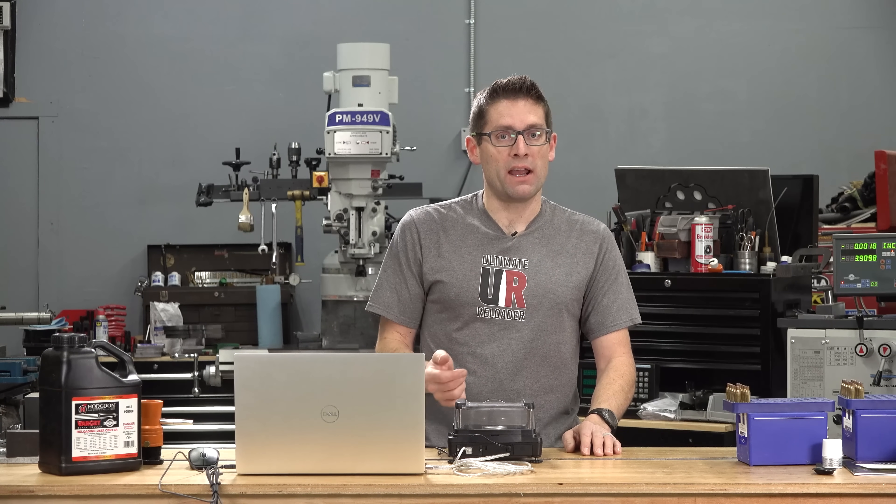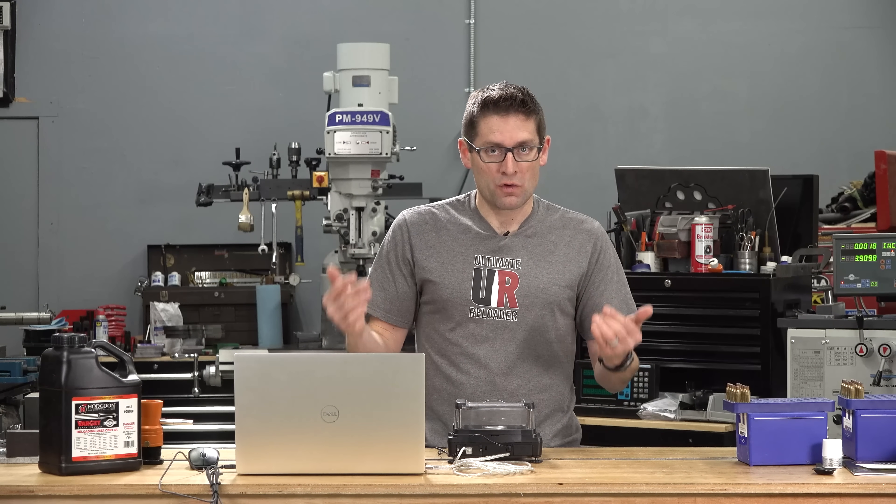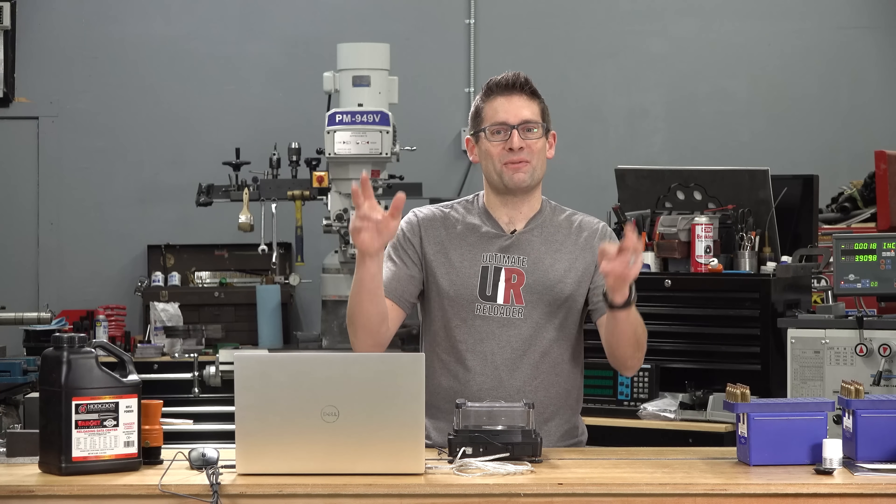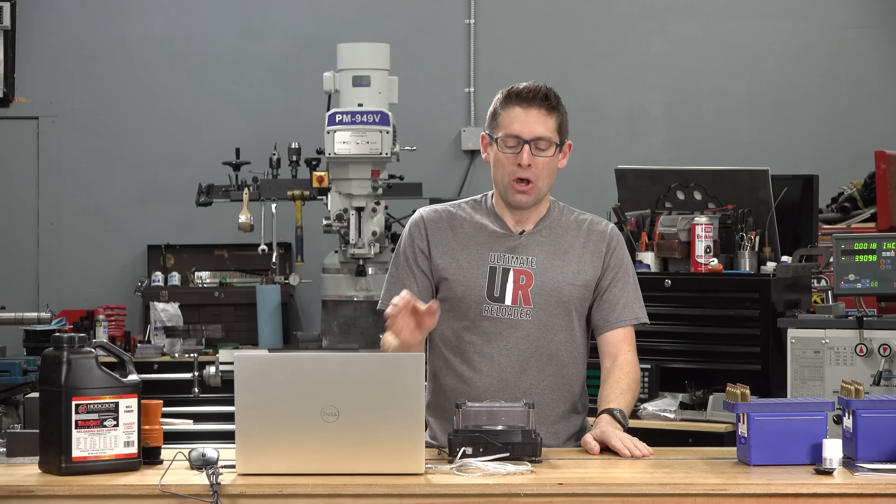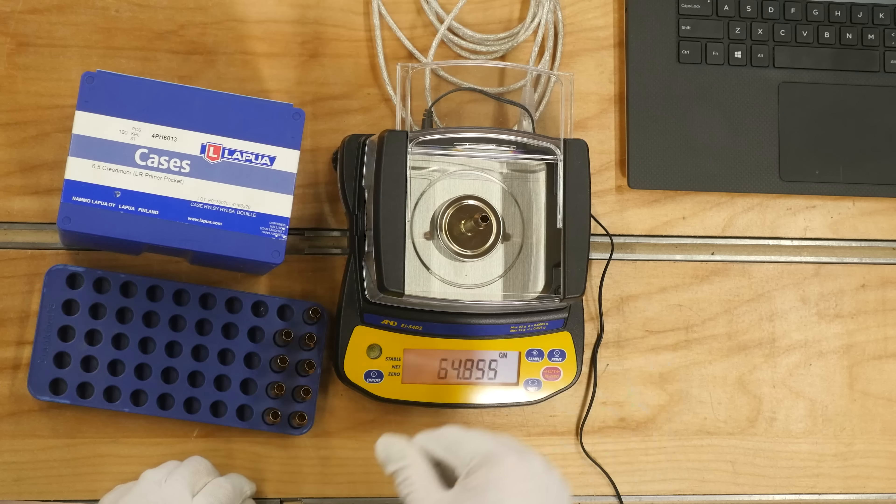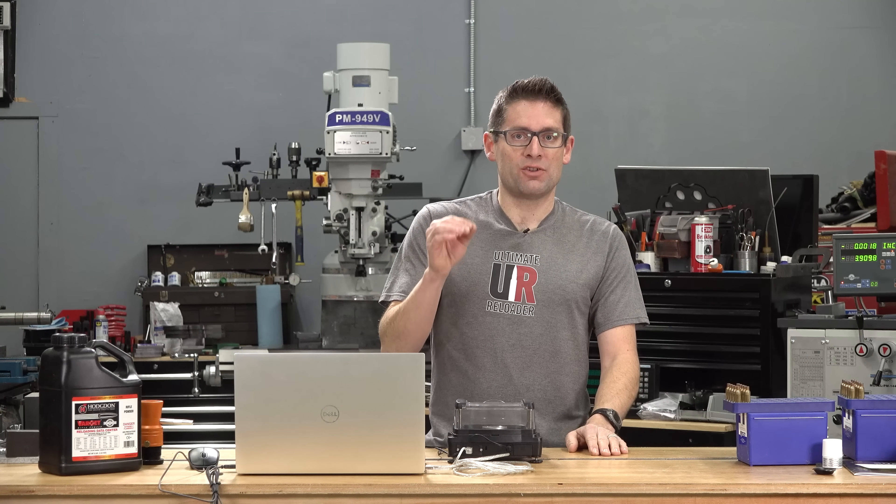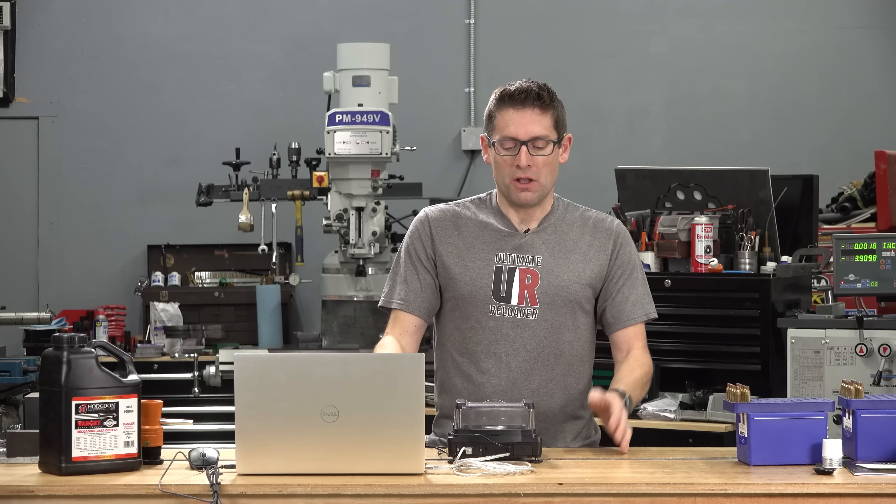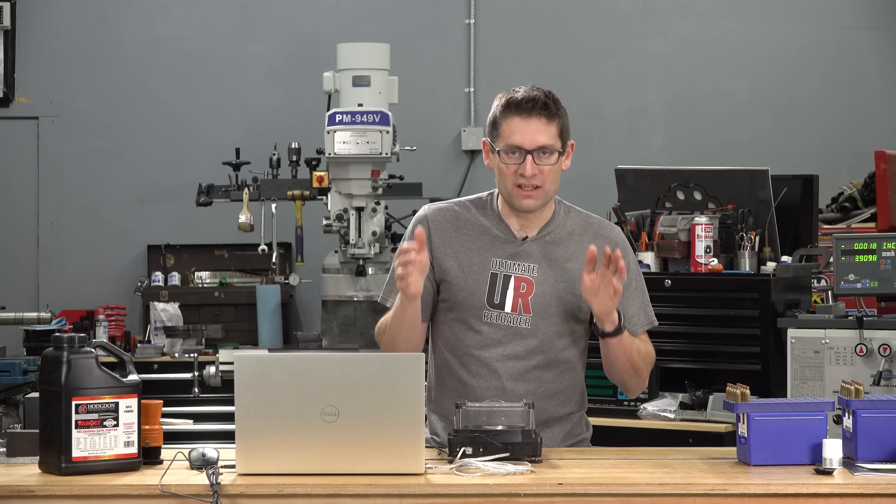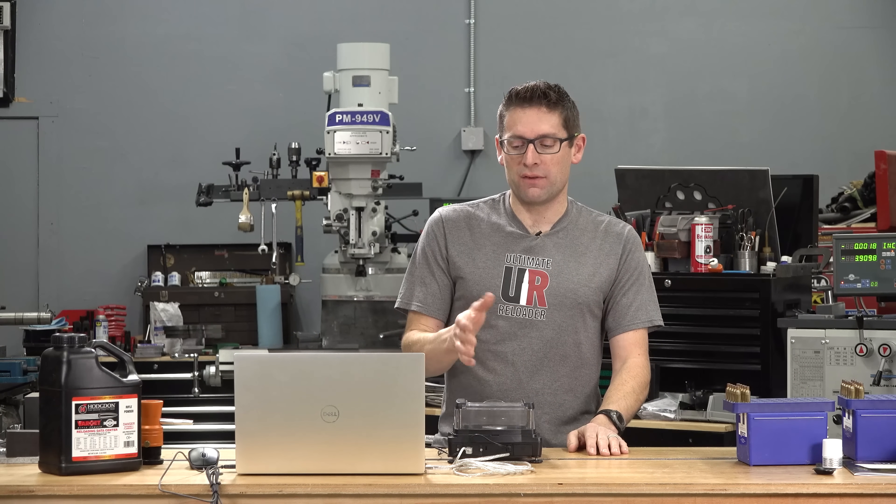Whereas the A&D FX120i can handle about 1500 grains. So they're kind of on a little bit of a different scale, if you will. I also noticed that this scale has a longer settling time. The FX120i, for instance, comparing the two, has a very fast acquisition and settling time. So different price points, different accuracy levels and different capabilities.